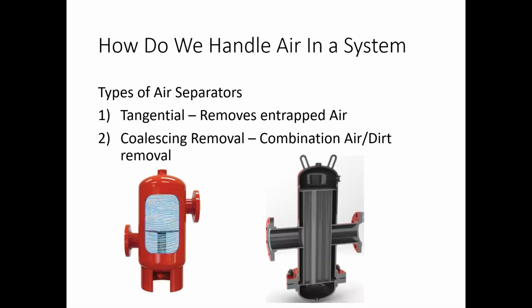There are two main types of air separators we focus on. One is the standard tangential air separator, which simply removes air. The second, becoming more popular, is the coalescing type, which combines air and dirt removal. There are pros and cons to both - that could be a topic for a different day. On the bottom left is your standard tangential air separator, and the bottom right shows the coalescing type.